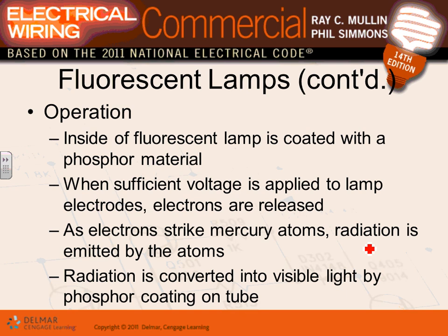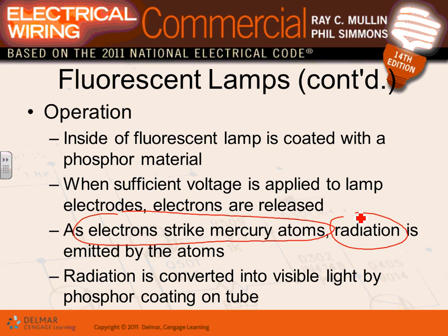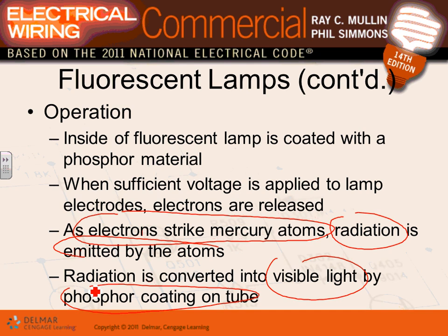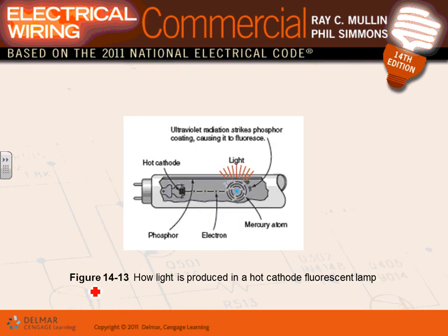Inside the lamp coated with phosphorus material, you heat the cathode, create an arc by pumping the voltage high, and the ballast maintains the arc by controlling the current so the circuit breaker doesn't trip. Sufficient voltage is applied to the electrodes — electrons strike the mercury atoms, releasing radiation. That arc releases electrons that hit the mercury atoms, creating UV radiation. The phosphorus coating inside the tube converts that ultraviolet light into visible light.